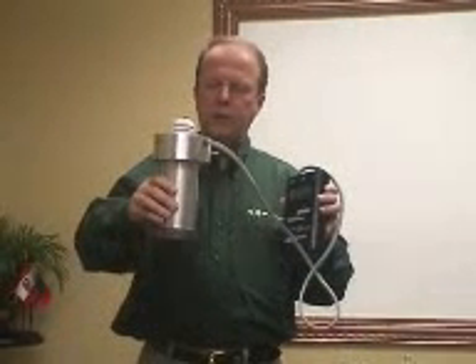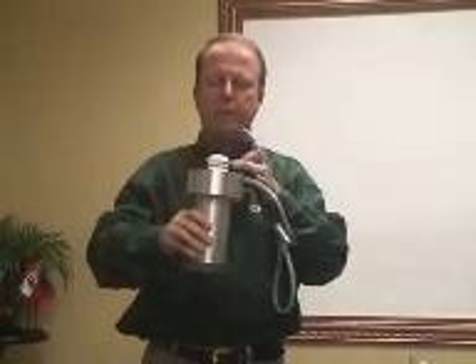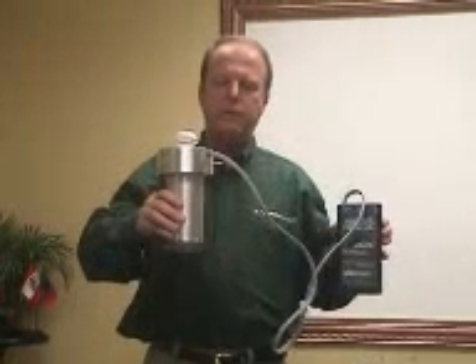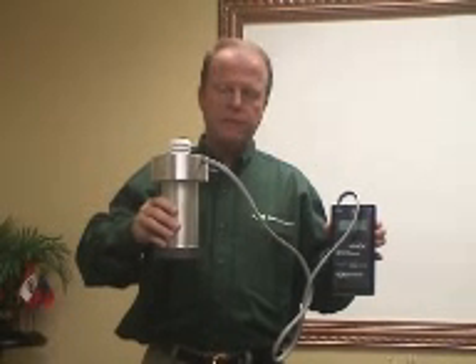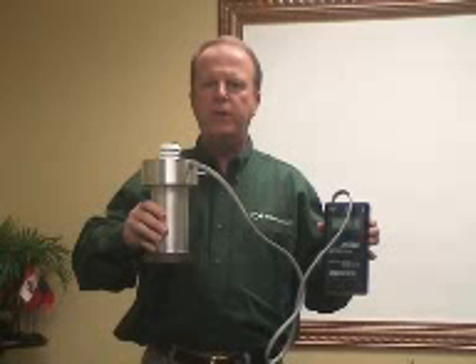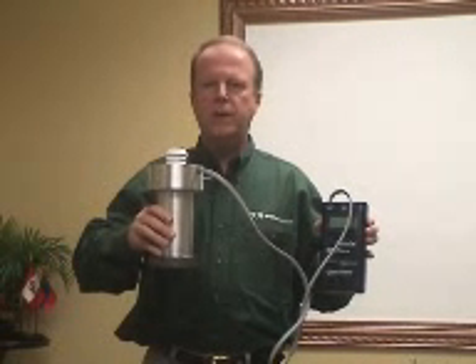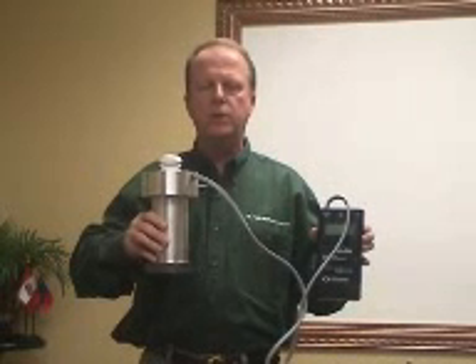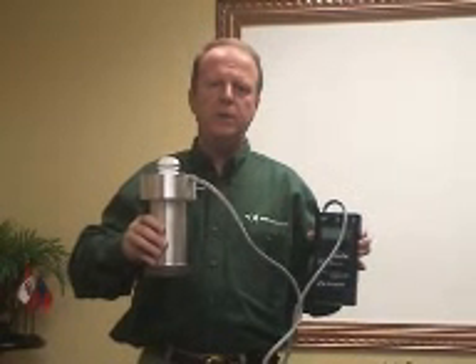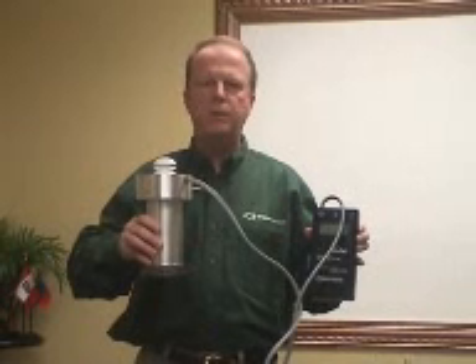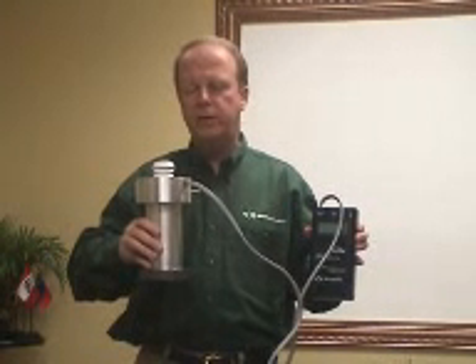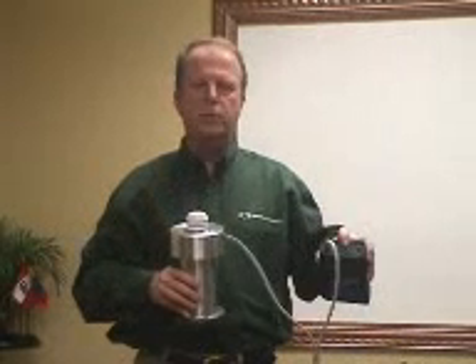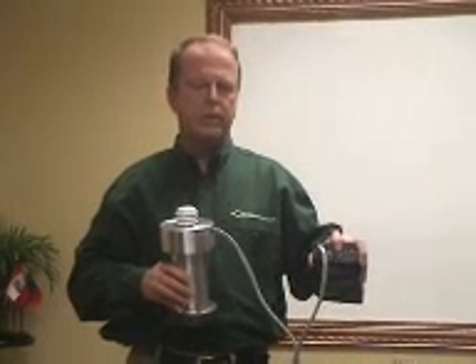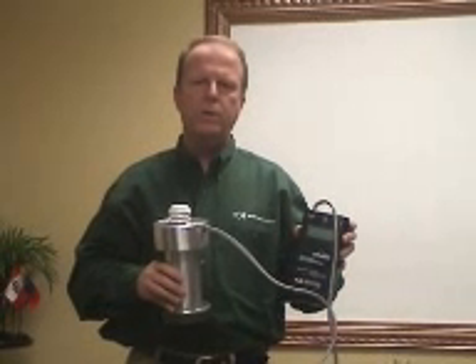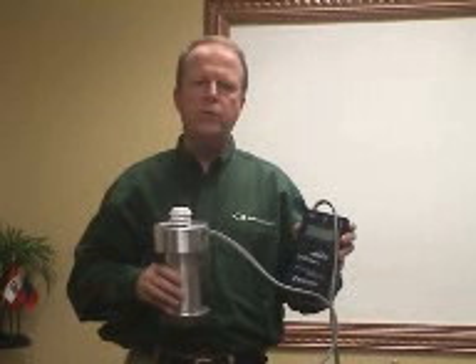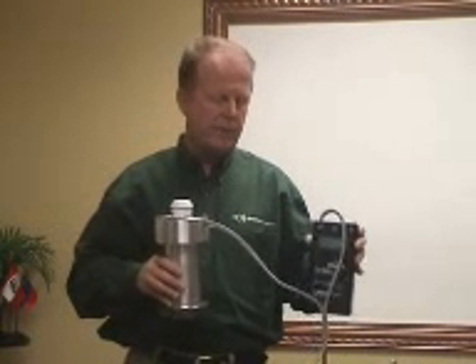You have a top-loading orifice device and an ambient temperature sensor. The range of this flow device is 7 cubic feet per minute up to 54 cubic feet per minute. So it covers a broad range of applications, including the traditional TSP, PM10, and PM2.5 high-volume air samplers made by General Metalworks and Tisch Environmental. Again, it has the RS-232 connection, and the software is provided with the unit so that you can generate your reports and put them into your folder as a verification and certificate of calibration.